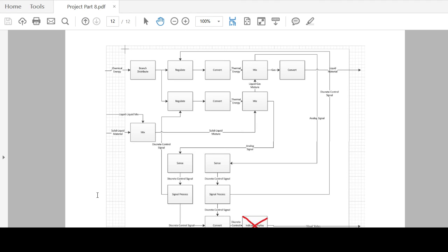Finally, this is similar to the failure looked at in Figure 8. The display itself could fail. Everything else in the system could work perfectly fine. The display, however, could get waterlogged, the screen could crack, and something like that could cause an engineer to, again, shut down the entire laboratory to assess the function of the incinerators, just because they aren't getting proper feedback on how the system's running.